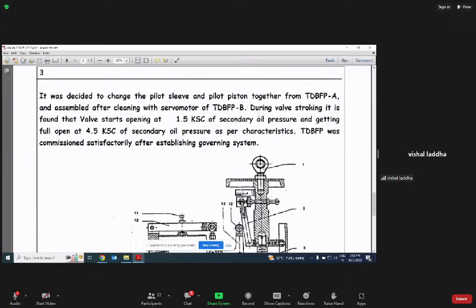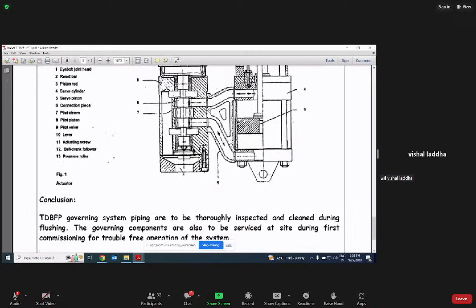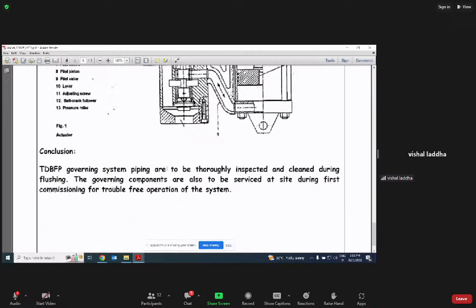During valve stroking, it was found that the valve starts opening at 1.5. Now it is correct, 1.5 to 4.50 for 0 to 100%. It means the problem was with the pilot sleeve and pilot piston, because they did not have much clearance. That is why it was not operating within range. So the TDBFP governing system was thoroughly inspected and cleaned. The governing component was also taken in service.